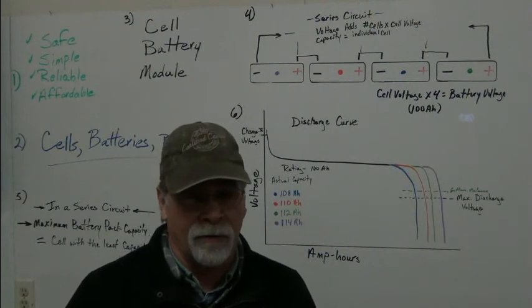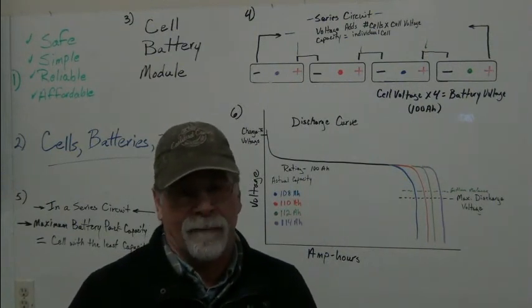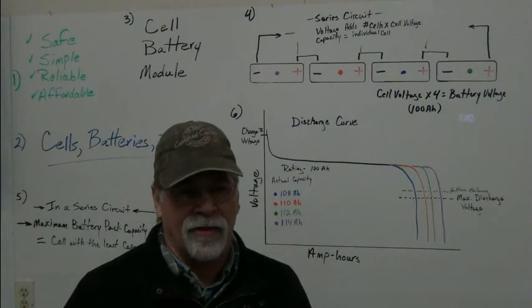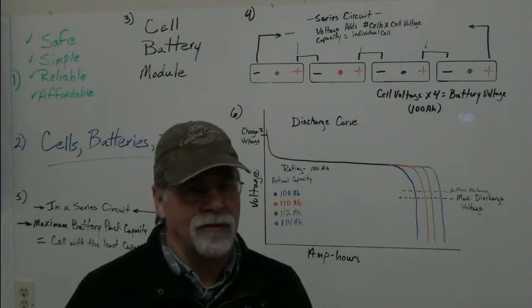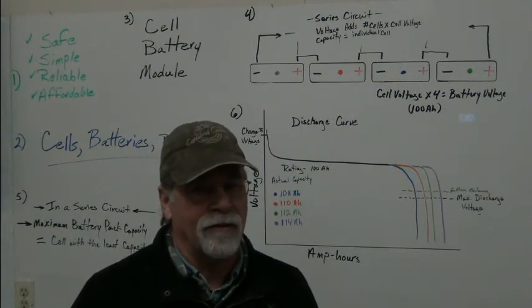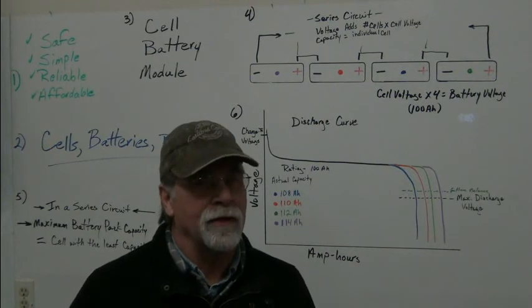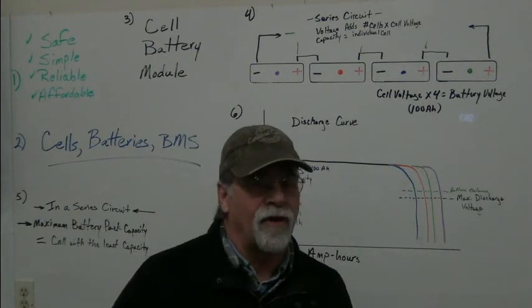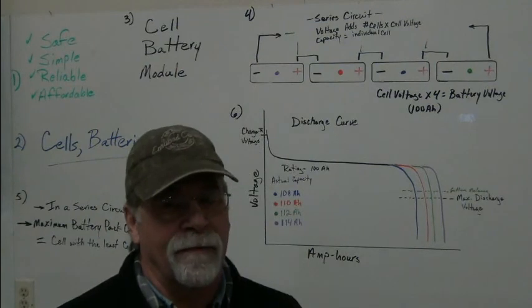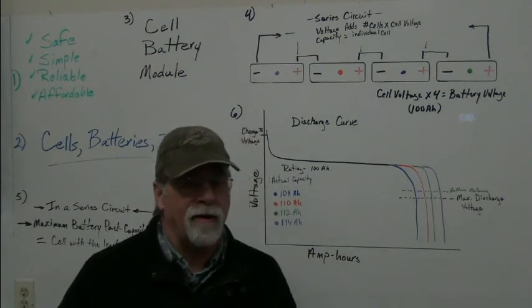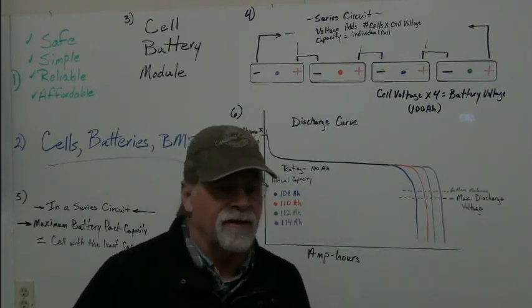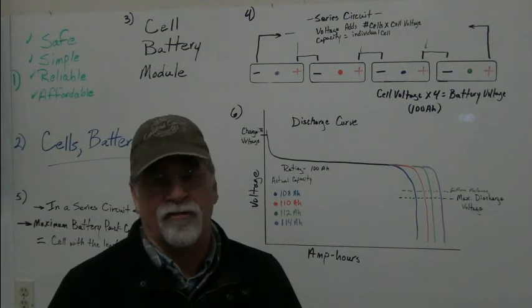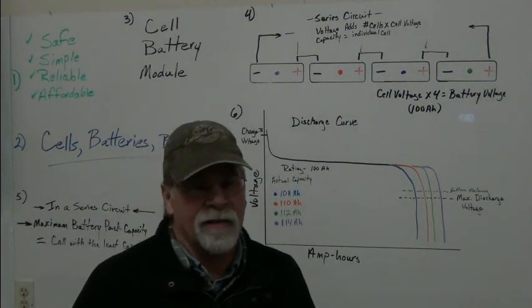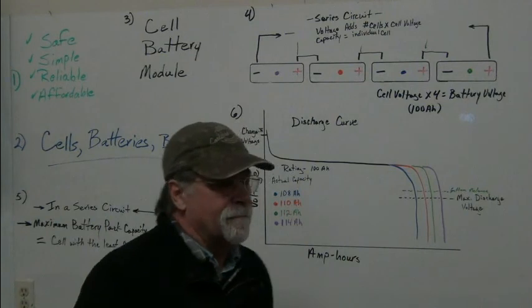But other cell chemistries, if you overcharge them, they're going to go into thermal runaway. NMC, I believe, is around 320 degrees Fahrenheit for thermal runaway. Lithium iron phosphate is around 512. So big difference. Lithium iron phosphate is very stable, it's the safest chemistry, safer than lead acid. It's the safest chemistry currently available.